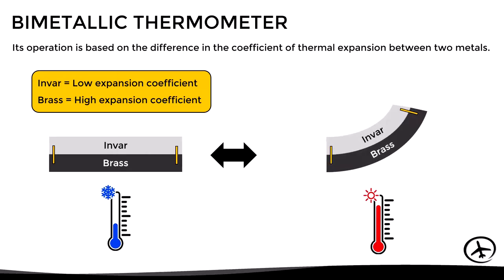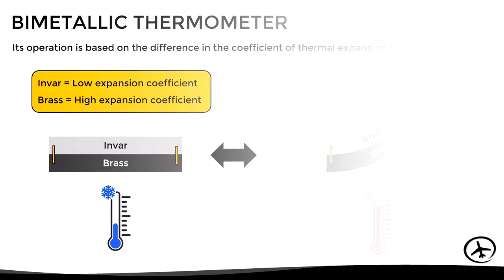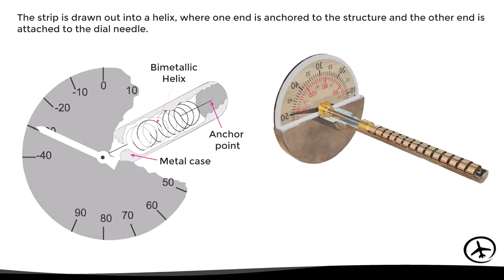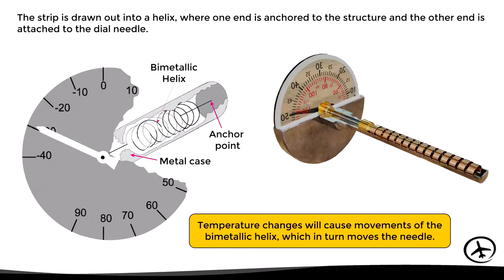In practice, these strips are welded together so that as the brass expands more than the invar, the whole piece will bend. This way, the strip is drawn out into a helix inside a metal case, where one end is anchored to the structure and the other end is attached to the needle. Temperature changes will cause movements of the bimetallic helix, which in turn will move the needle to indicate the current temperature.